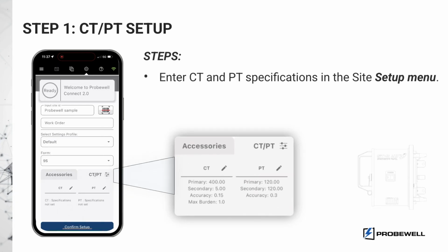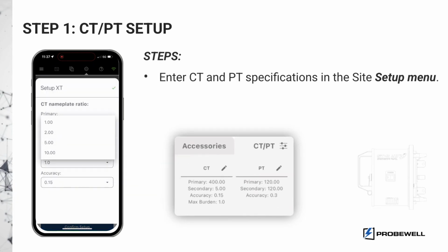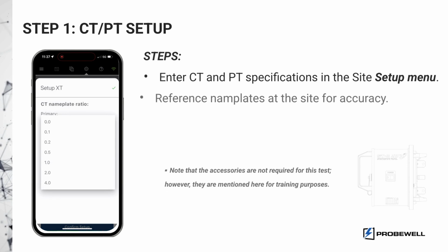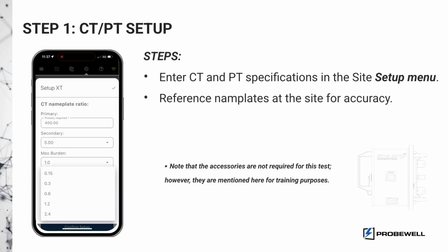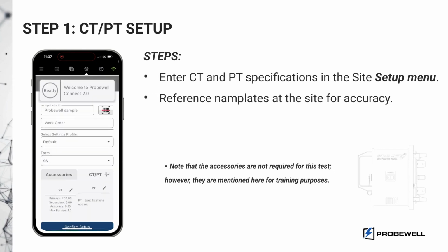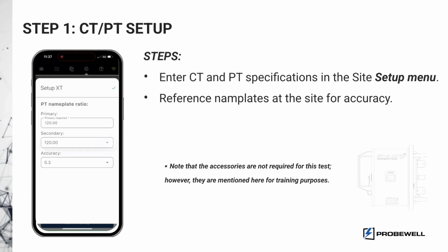In the site setup menu, enter the correct CT and PT specifications. This guarantees accurate power quality test results. You can find this information on the CT and PT nameplates at the installation site.